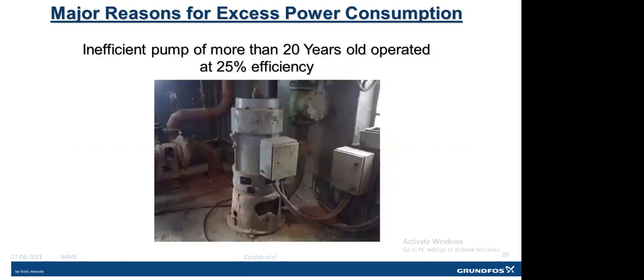This is one of the examples where we replaced a 20-year-old pump which was operating at 25% efficiency. This pump had a motor of 37 kilowatts, and we replaced it with a motor of 22 kilowatts.